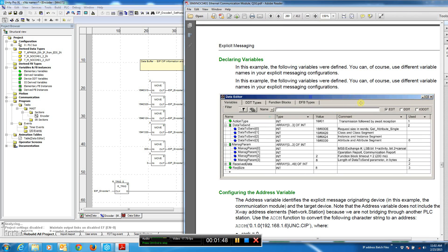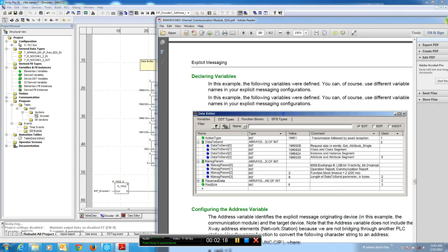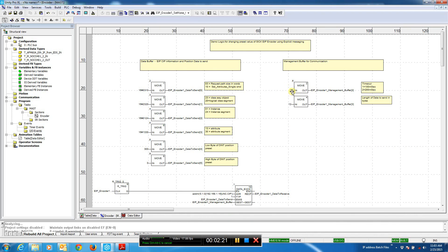So we come here and take a look at the actual management parameters — it's actually pretty simple. The first two words in the array are read-only, so we don't need to do anything with that. The third word is the timeout of the block itself: one would be 100 milliseconds, two would be 200 milliseconds for the timeout. The last parameter in the management parameter is the number of bytes to send. In the example given in the manual it was just getting a value so they used eight; in our example we're going to set with 12. We're going to have a timeout of two in the data buffer.